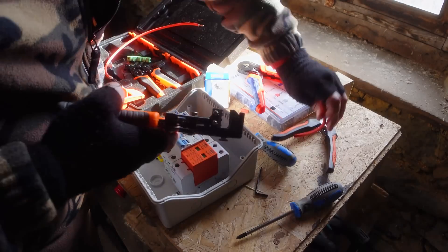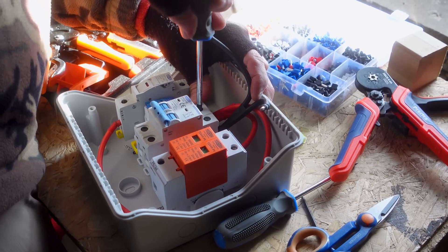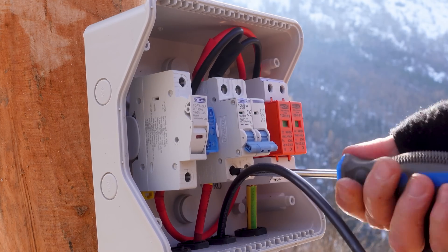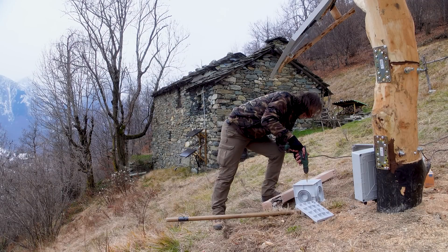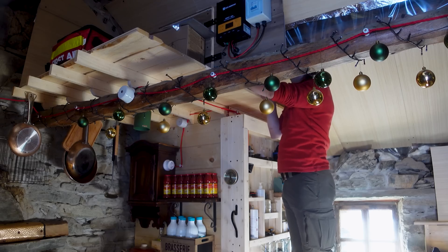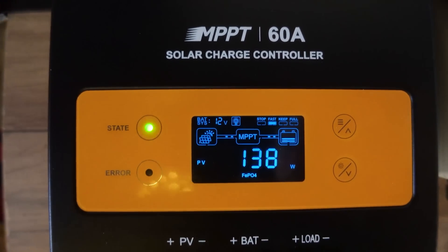To protect the system, I assembled a combiner box with all the necessary safety features: fuses, DC circuit breakers, and surge protectors, directing power to the cabin. I installed a grounding pit just one meter from the solar tree. For added safety, I installed another disconnect switch inside the cabin to isolate the panels during storms, ensuring I don't have to go outside.